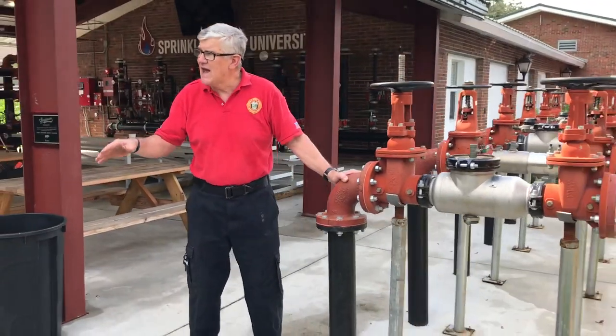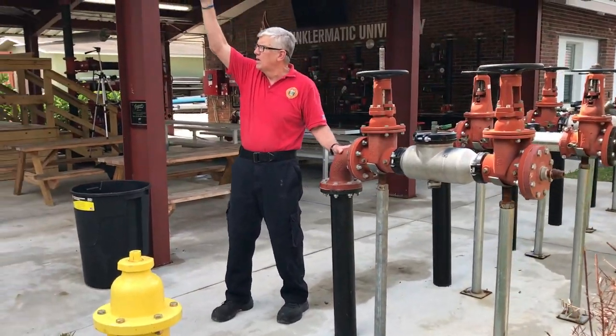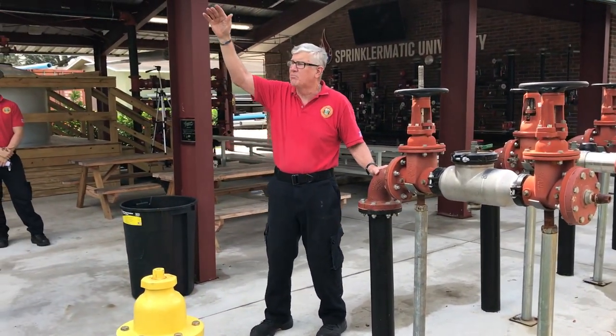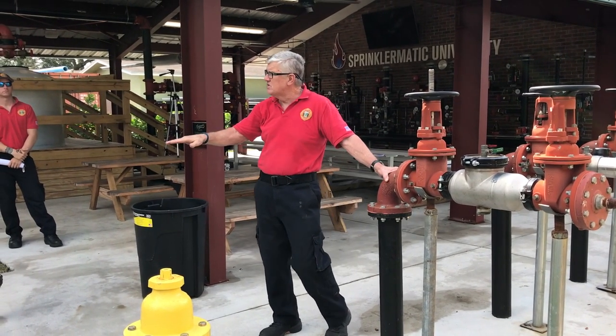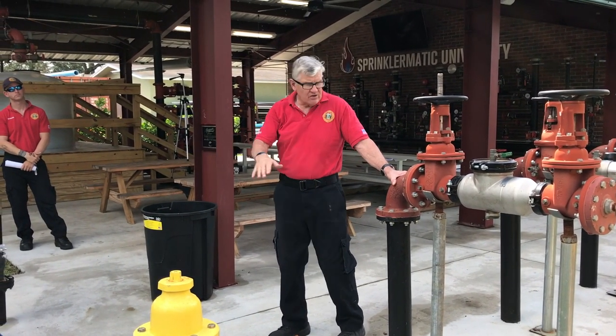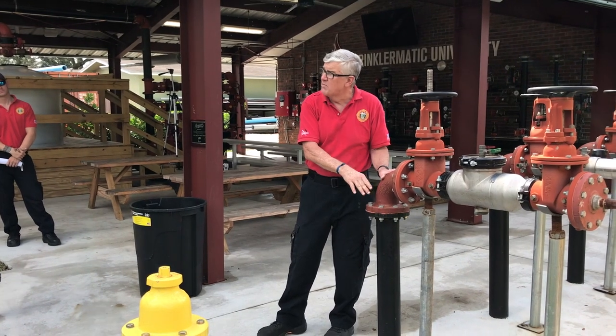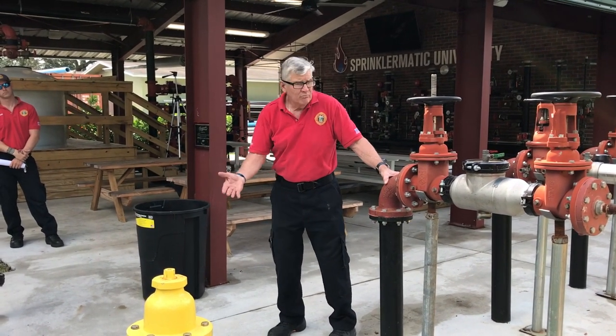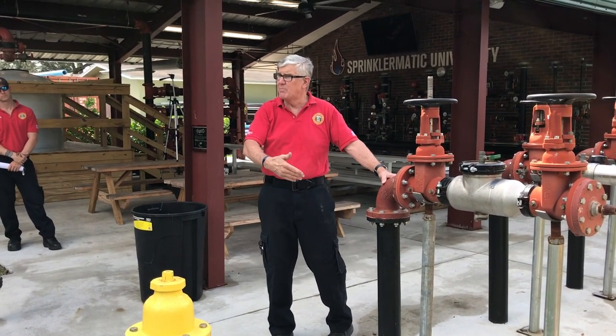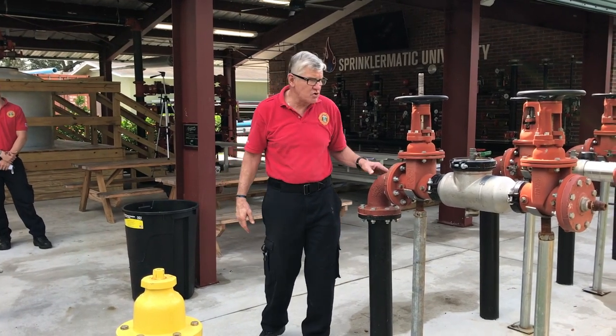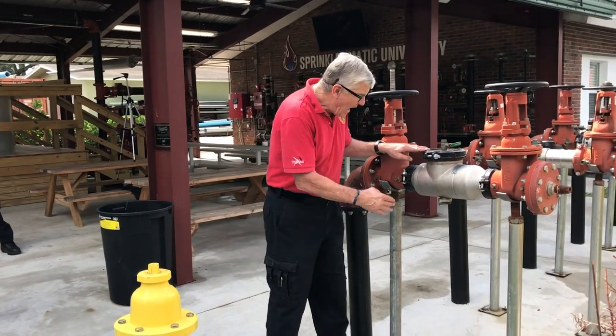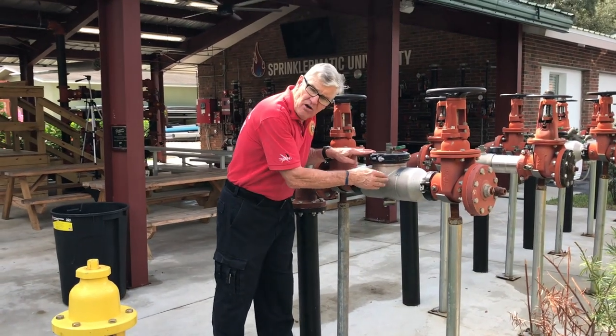We explained in the class that we've got a 30-story building with 150 pounds of head pressure exerted at the base of that riser. You got 70 pounds of water in your water main, let's say. We don't want that putrid water ending up in the potable water supply. So what you have in here are two check valves, two.